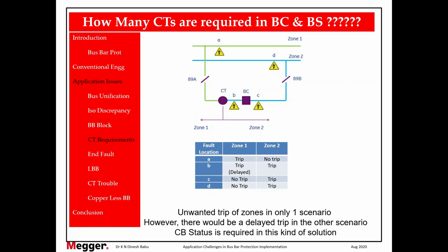So we are putting an OR gate. What are the conditions when I should remove the bus coupler CT from the zones? Condition number 1, breaker feedback should come: the 52A contact should be low and the 52B contact should be high. Okay, what I told is right. Second condition, whenever the other zone, that is zone 2, trips, after a certain time delay that is greater than your breaker operation time, we will directly remove the CT from the zone 1 algorithm. So these are the pros and cons.